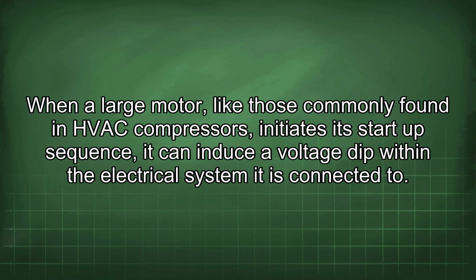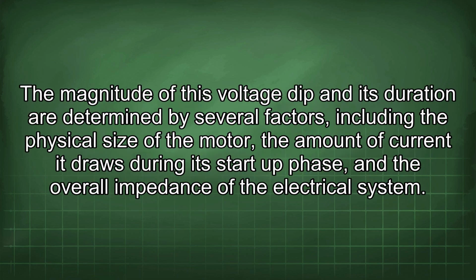When a large motor, like those commonly found in HVAC compressors, initiates its startup sequence, it can induce a voltage dip within the electrical system it is connected to. The magnitude of this voltage dip and its duration are determined by several factors, including the physical size of the motor, the amount of current it draws during its start-up phase, and the overall impedance of the electrical system.